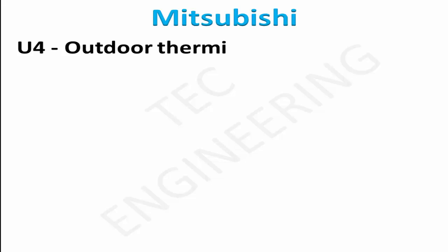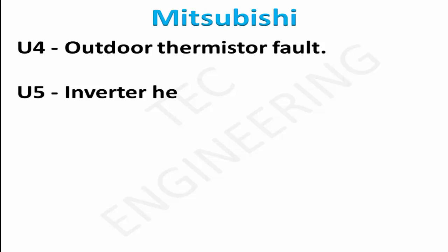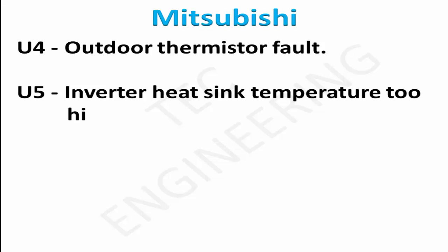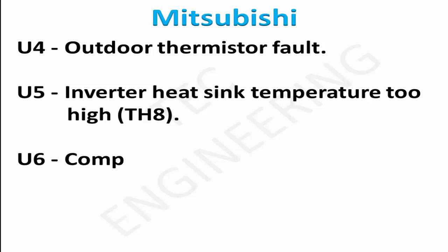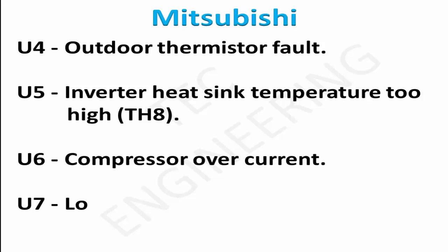U5: inverter heatsink temperature too high. U6: compressor over current. U7: low discharge superheat.